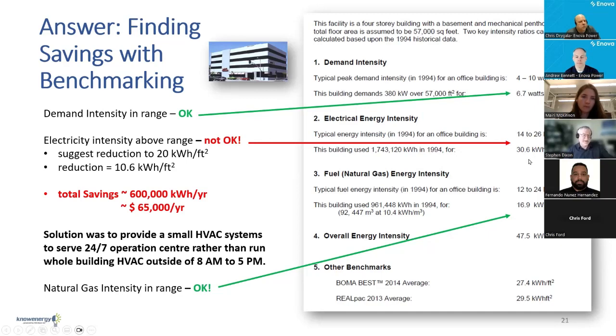So I started asking a few questions, and it turned out they had an operations center on a quarter of one floor for which they ran the entire HVAC system. We estimated, without even going near the building, that if they could bring that 30 back down to a 20, that'd be about $65,000 a year in savings. That justified them doing an energy audit, and the energy audit found exactly what I'd found from the benchmark.